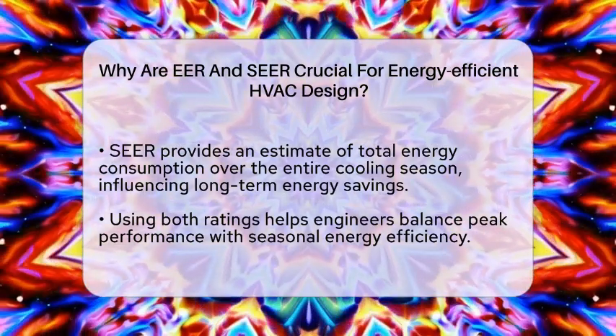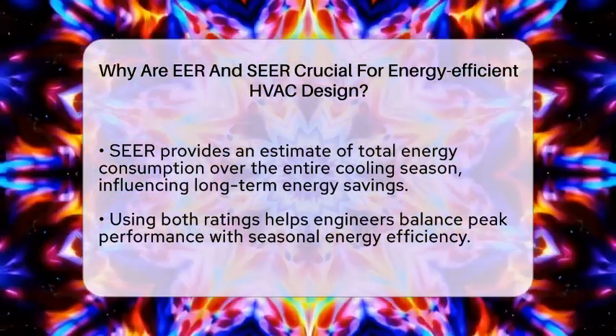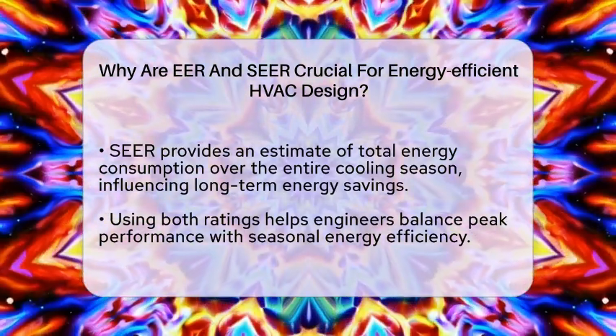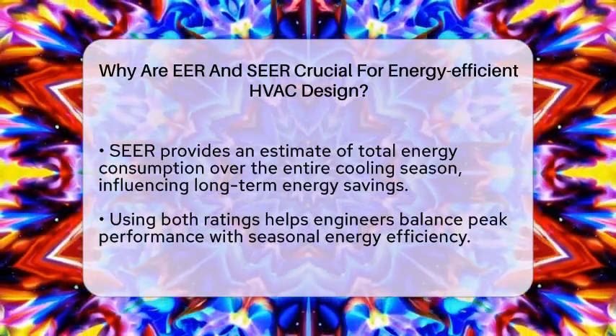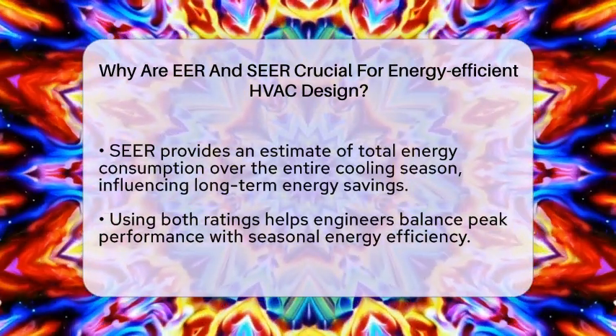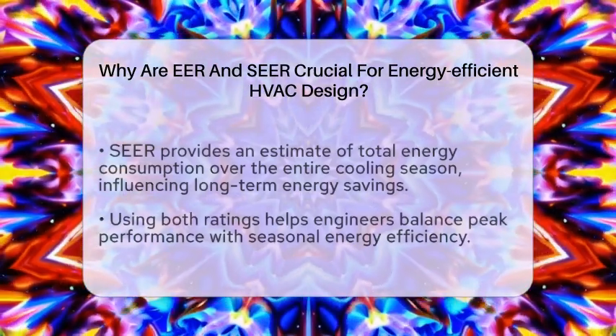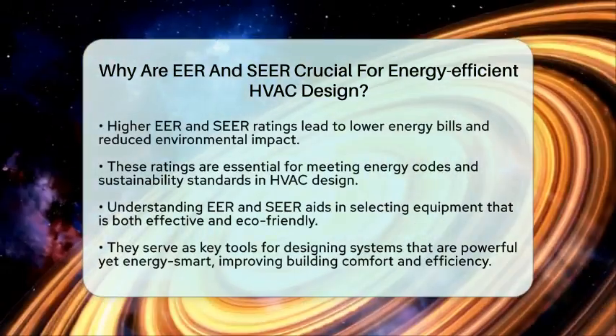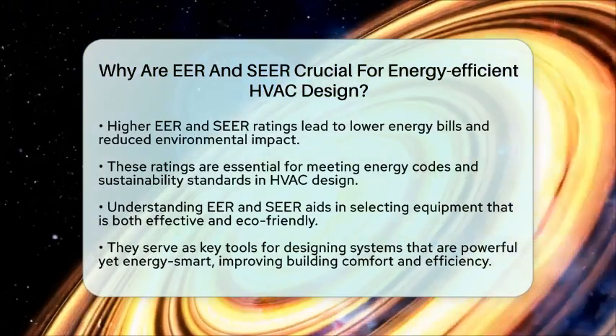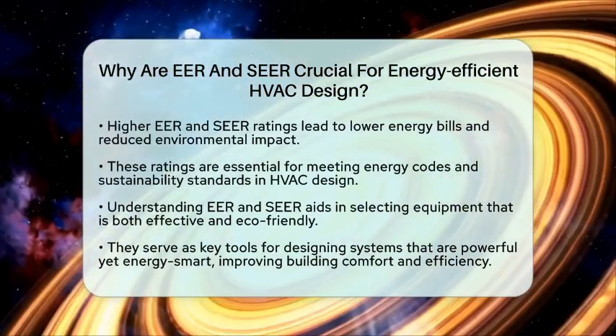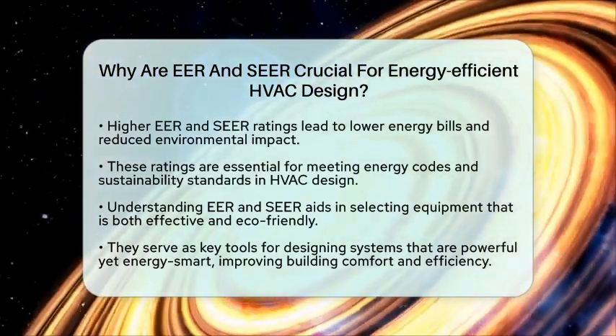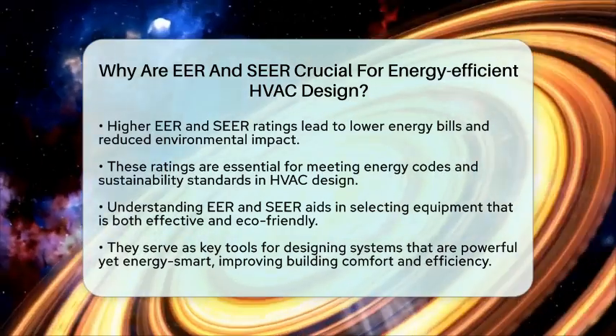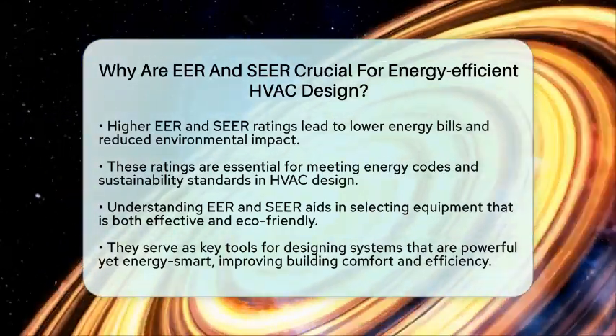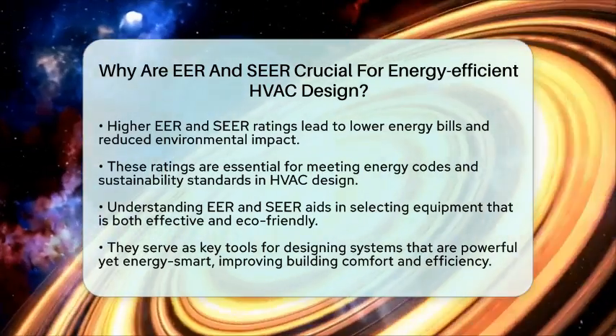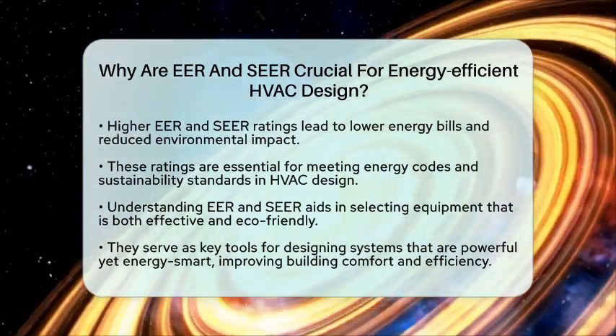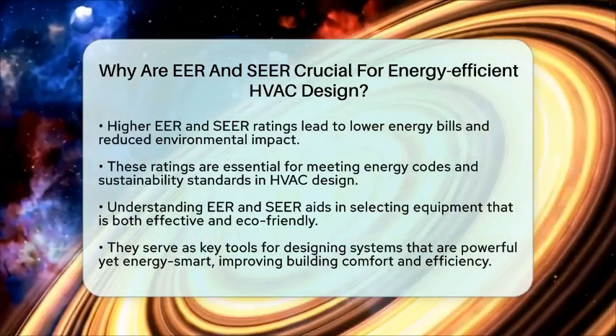Using both EER and SEER together allows engineers to balance peak performance with overall seasonal efficiency. This is especially important in climates where temperatures vary a lot or energy costs are high. When selecting equipment with higher EER and SEER ratings, the system will use less electricity, which means lower utility bills and less environmental impact. For HVAC design, understanding these ratings helps meet energy codes and standards.